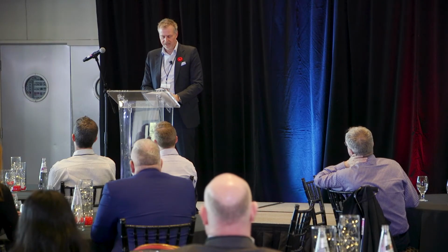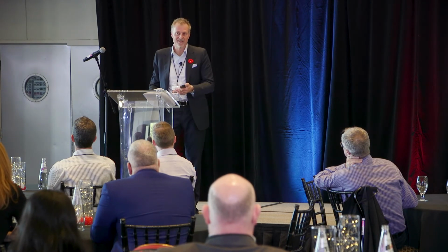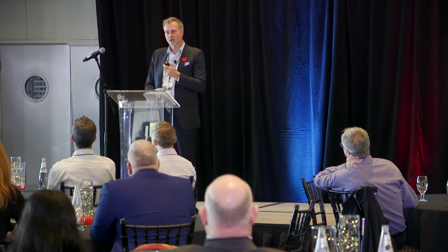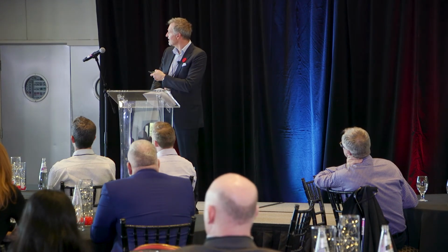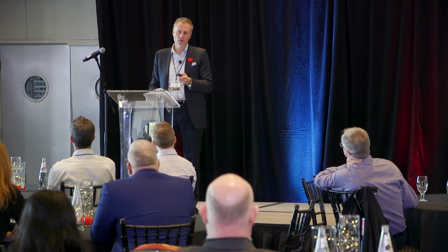We've run into situations where, for example, Toronto Housing had a building with multiple risers, and they had cold spots within that building. Originally they were running off of sensorless with that control curve. Because of the multiple risers, we had to increase the head required, and so we moved from a quadratic to more of a flat line. Now, we're not meeting ASHRAE 90.1, but we're solving a comfort issue in that building because of the way the system has been set up. So the point here is that there's a distinct advantage in this technology being applied correctly, but understanding how it works is the first key to that.